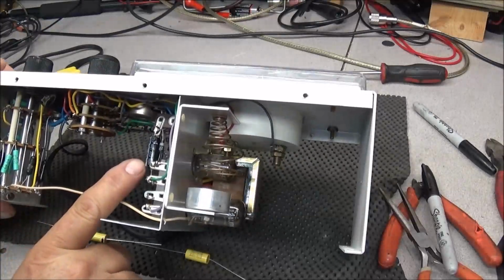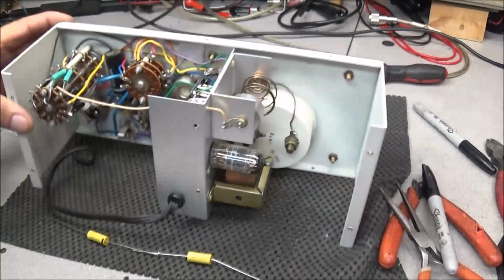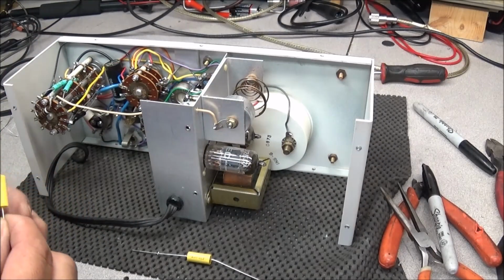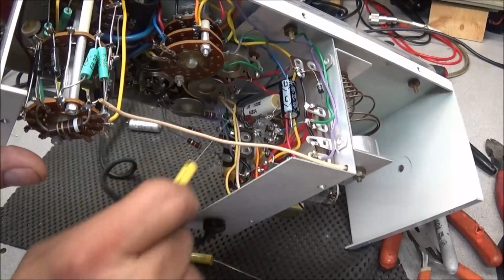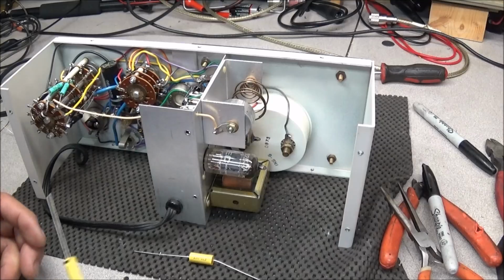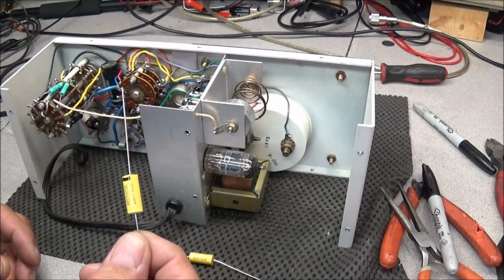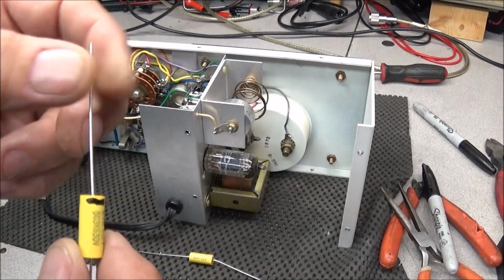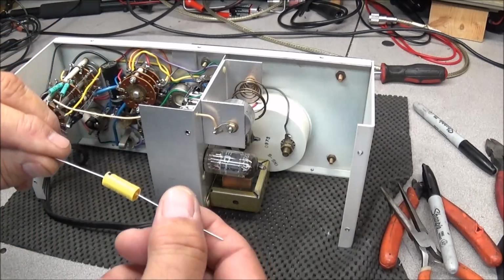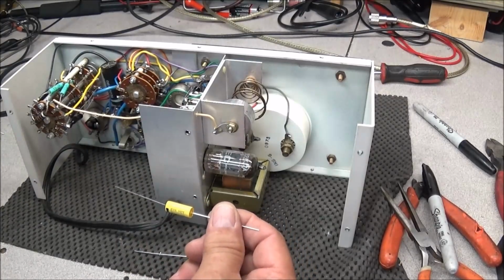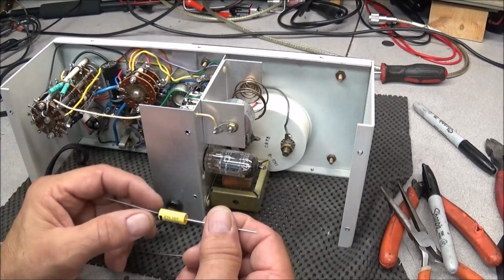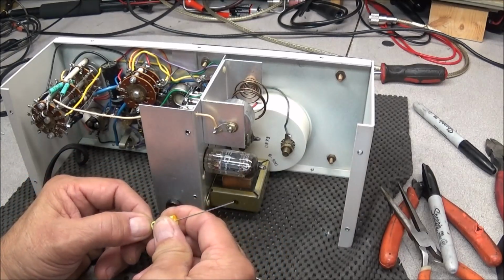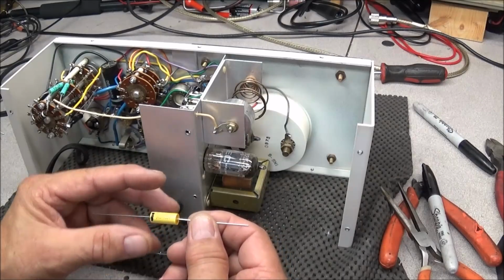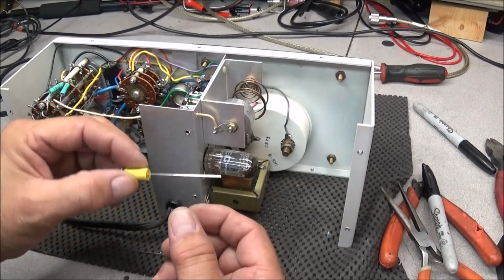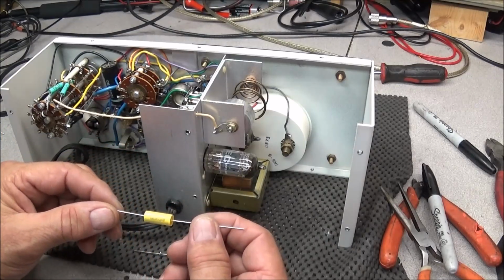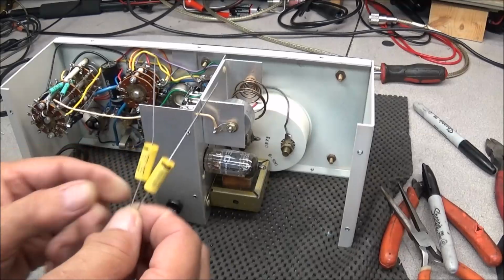Alright, I got our electrolytic here installed, and now I want to go ahead and replace the 2 0.05s at 400 volts, and I'm replacing them with 0.05s at 600 volts. And I've already marked the ground side, and the reason being that, well, I'll leave a link down below to Paul over at Mr. Carlson's Lab, where he'll explain that to you. But you want to make sure you have your ground on the outer side of the foil on these, not connected to the inside. So now we'll go ahead and get both of these installed.